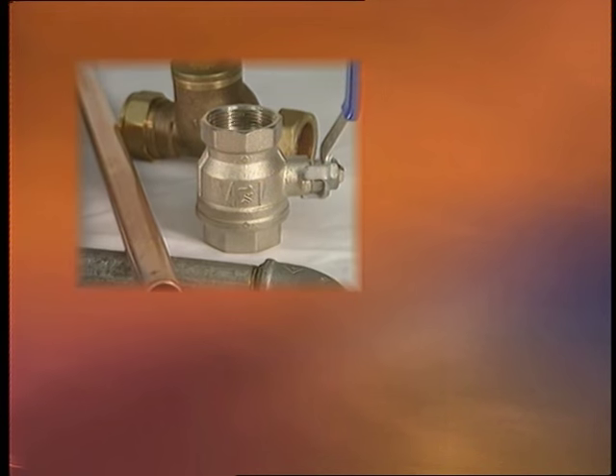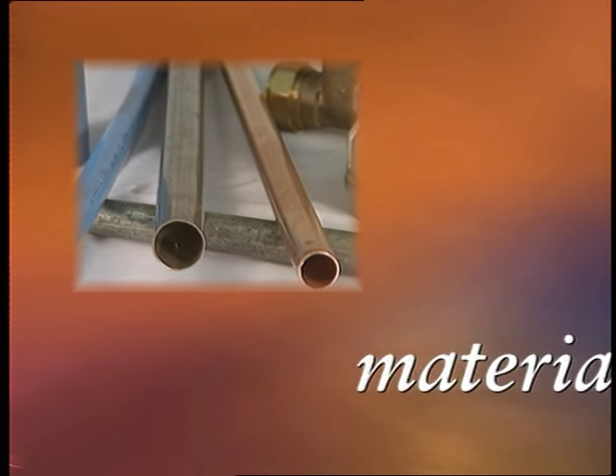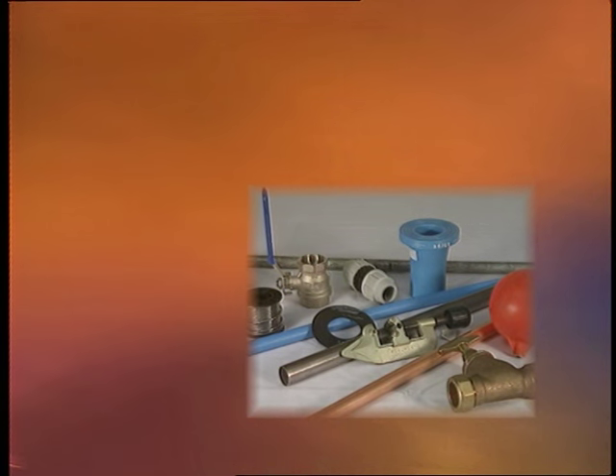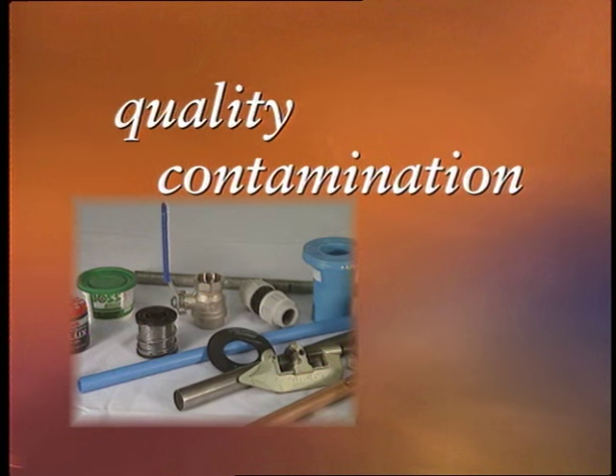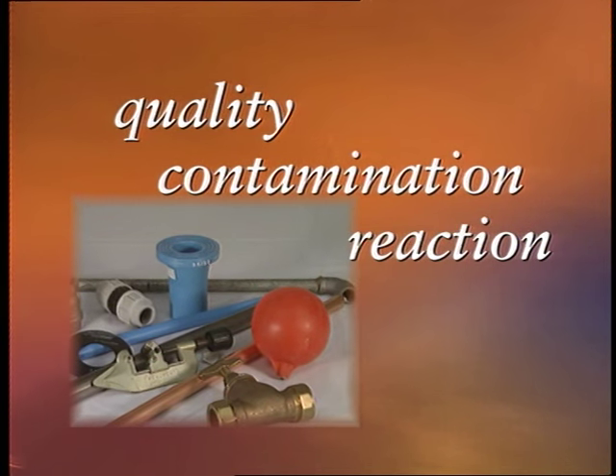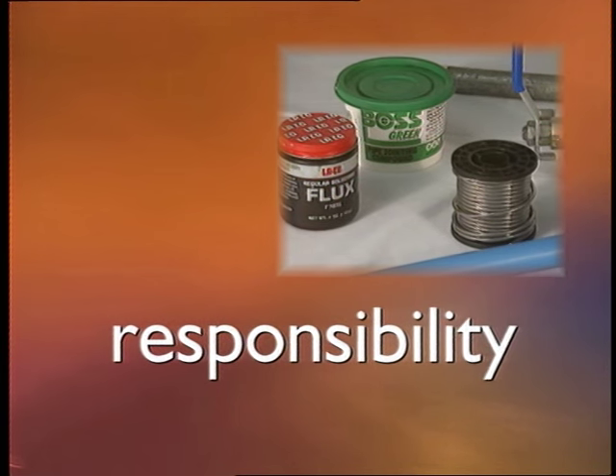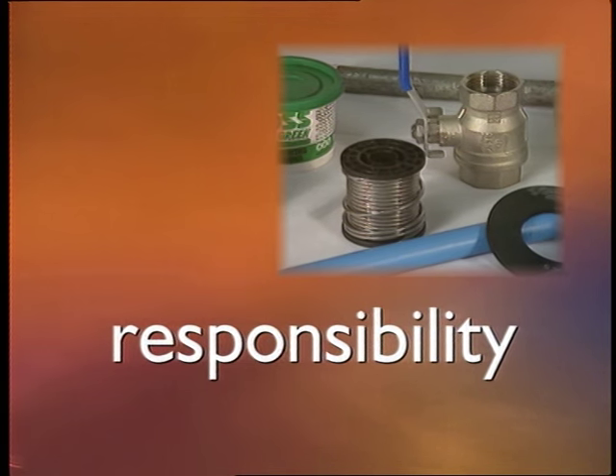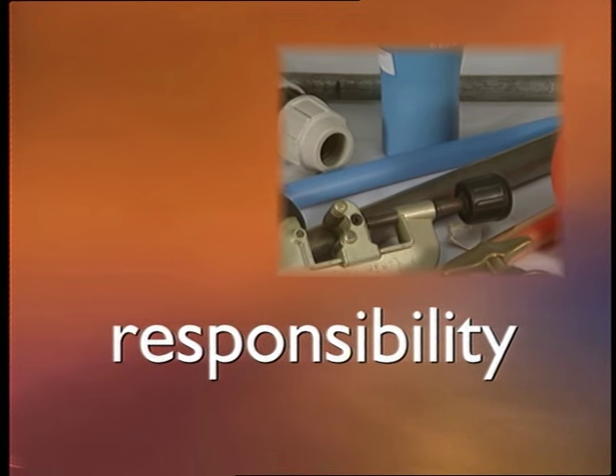Let's consider the regulations concerning the materials you use. Materials include all metallic and non-metallic substances, including plastics, used in the manufacture of pipes, fittings and appliances, as well as those used for jointing and protective coatings. Anything you use which can come into contact with water mustn't affect its quality, contaminate it in any way that affects its drinking qualities, or contain substances that might leach into the water, react with it, make it toxic, biologically unhealthy, or affect its colour, taste, temperature or smell. The manufacturers of all the materials you use are also responsible for meeting the regulations, but you can't just rely on them. It's your responsibility to know which materials you can use — you're the installer, and if any harmful substance was installed, you'd be the one prosecuted, not the manufacturer.